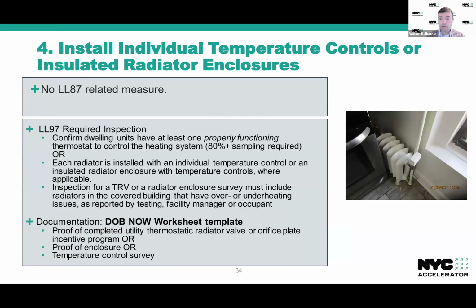And as far as the required inspections, there's going to be a minimum 80% sampling rate required for the retro-commissioning agent to look at apartments individually and confirm that there are functioning thermostats or individual controls on heating units. Or if there are not functioning controls, each radiator or heater needs to be installed with the appropriate control in order to comply with this measure. Also important to note that if during testing or an interview with building staff or occupants, it's discovered that there are certain sections of the building that are either over or underheated, those sections should be inspected to ensure that there are properly functioning controls or that controls are installed in those areas.